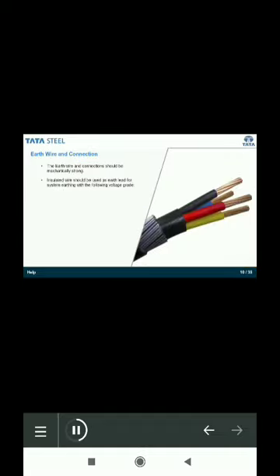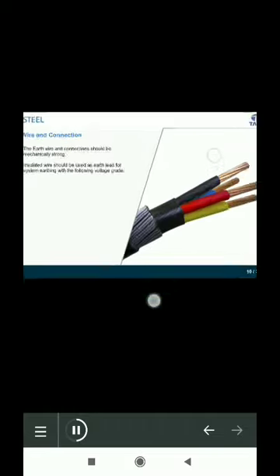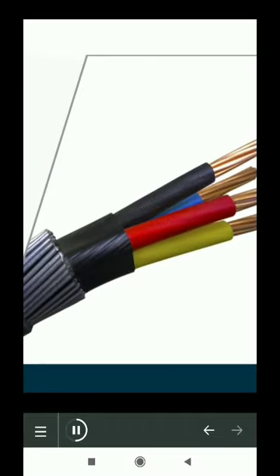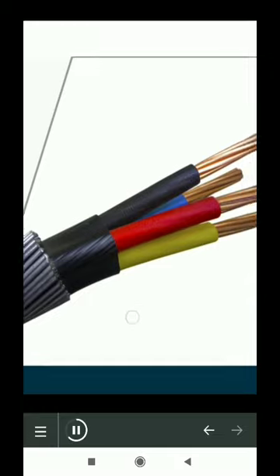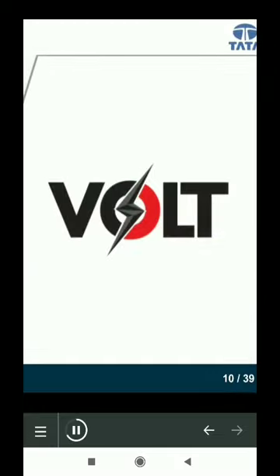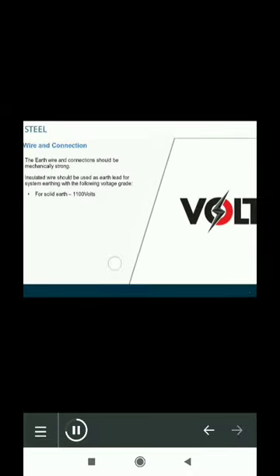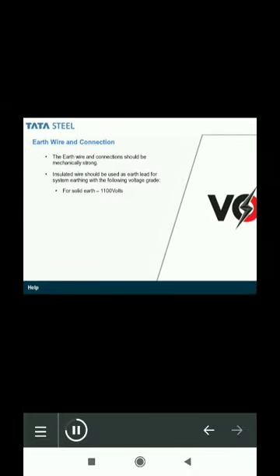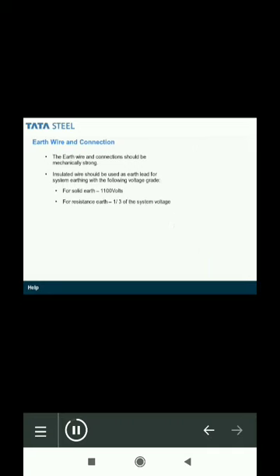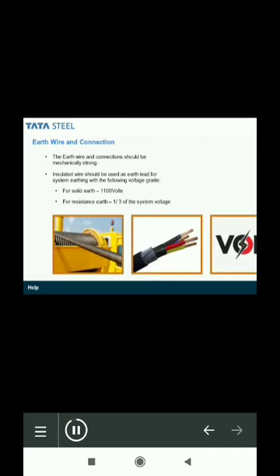So for earthing, insulated wires should be used as earth lead for system earthing, and their voltage rate is determined by the earthing type. If it is solid earth, then the insulation should have a rating of 1100 volts. If it is resistance earthing, then the insulation should have a rating of one third of the system voltage.